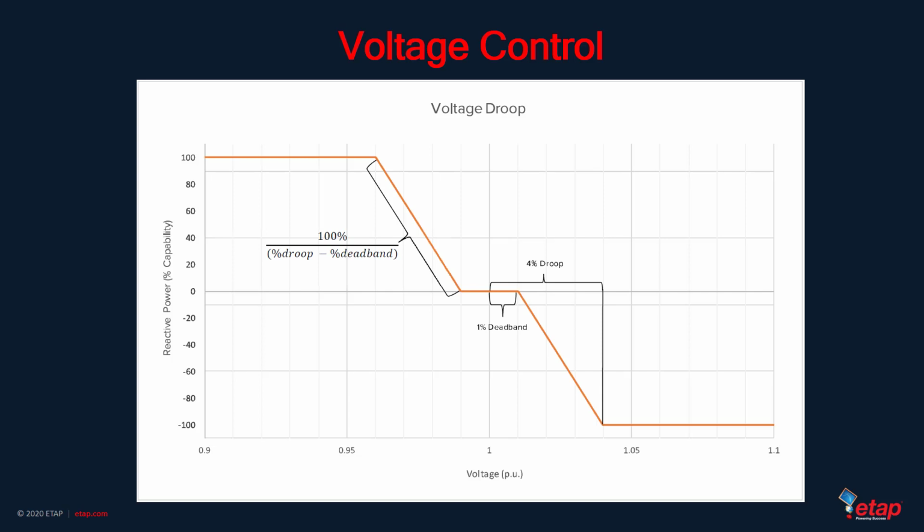export reactive power. To boost transmission voltage, voltage control mode injects reactive power into its output, boosting its overall apparent power. When system voltage is above nominal, the plant will begin absorbing reactive power to pull the voltage closer to nominal. Unlike other control modes, voltage control will only influence the system voltage and might not always hold at the specified set point, depending upon the strength of the system being connected to.